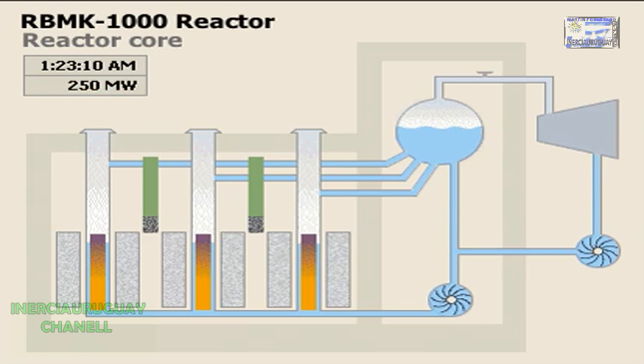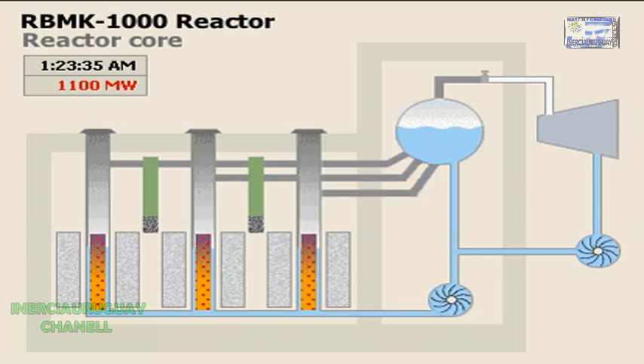Returning to the test procedure, the operators shut down steam to the single operating turbine generator. As the generator slowed, so did the cooling pumps. Inside the core, a buildup of steam was rapidly increasing the fission reaction. This generated yet more steam, which in turn generated more power. The reaction was now out of control.